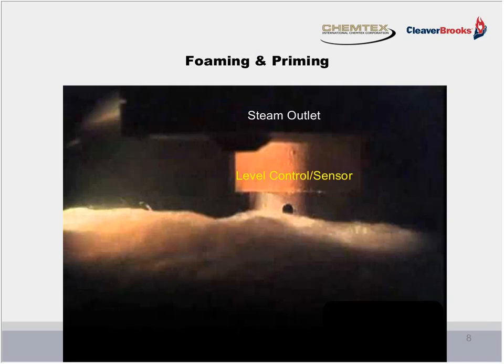This is an inside shot of a fire tube boiler with a probe-type level sensor extending into the water, and you can see the steam outlet located above it. Now, note the foaming and the priming occurring at the surface of the water, reducing its tension. Now, this will increase as a result of the increased solids forming at the water surface, especially contaminated condensate, which might be containing things like alkali, oils, fats, greases, and certain types of organic matter and suspended solids. But the result is the same, carryover into the steam main, and at times it can be considerable.